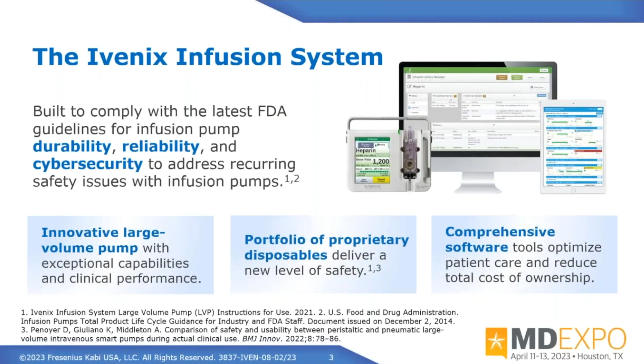So when you're doing your calibration checks in biomed and you're doing your preventative maintenance, one of your requirements is to take a tape measure and give the right amount of inches from the top of the water level down to the pump. We're immune to that. We don't care. That doesn't affect our calibration at all. The pump can actually pump laying on its back, on its side, upside down. If you think of what the devices go through when they're being transported, there's quite a bit that can happen, right? So we want to address real world scenarios on how accuracy is important for an infusion.